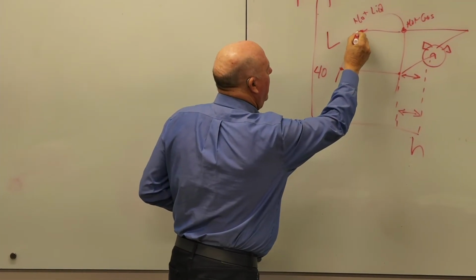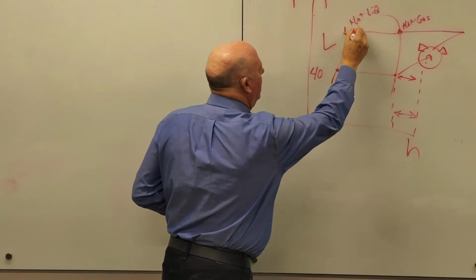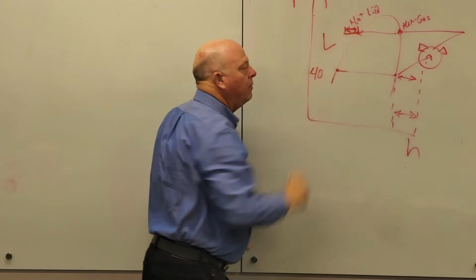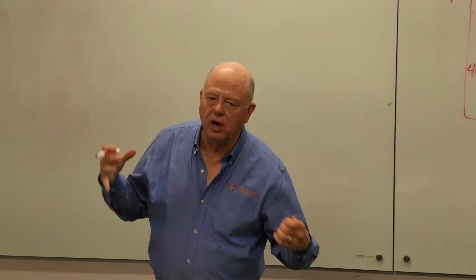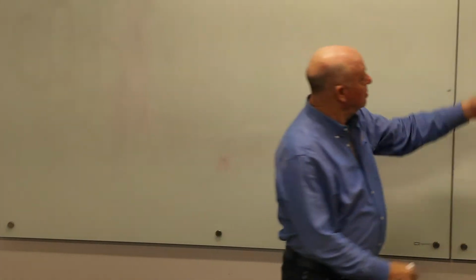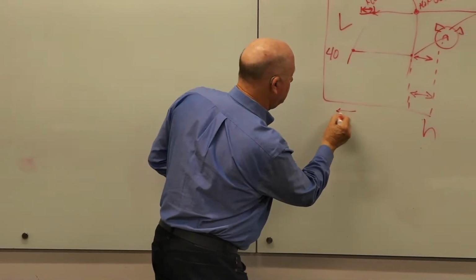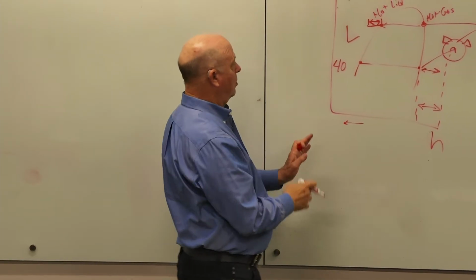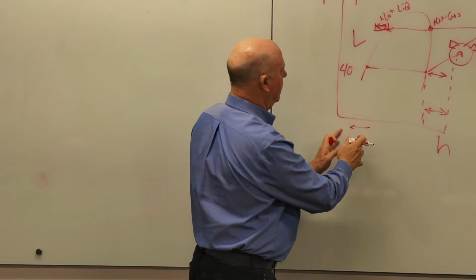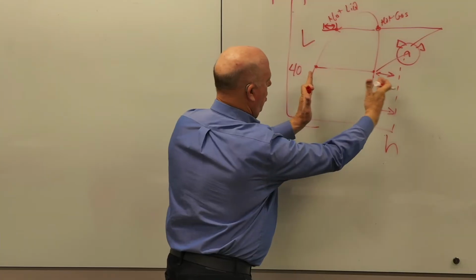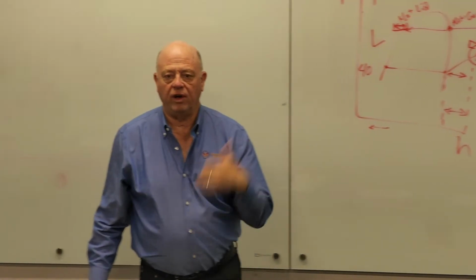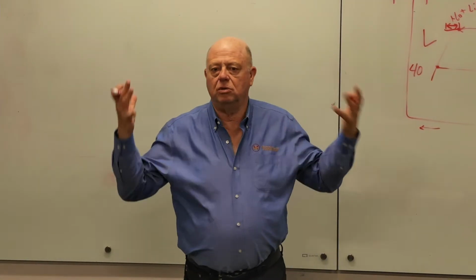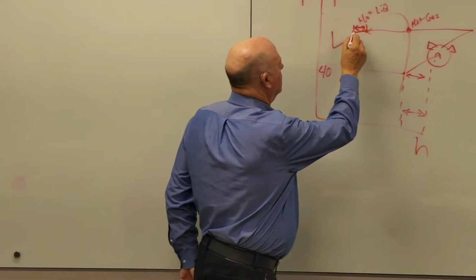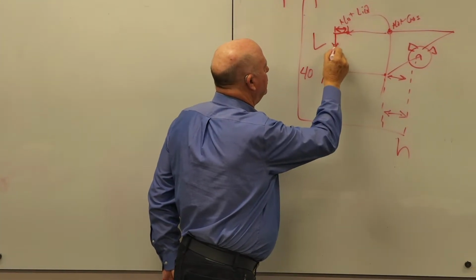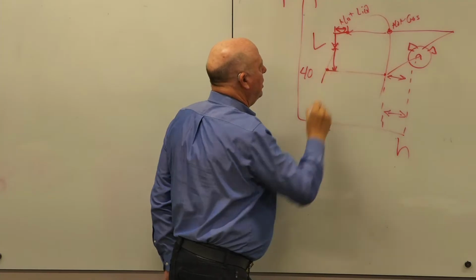To be sure that we got all liquid, we want to come over here a little ways and get some subcooling. Now I'm sure I've got all liquid. And you'll notice I've moved further this way. So that means that I am getting more cooling out of it if I give it some subcooling. So, that's good. We want to get some more subcooling. So we come down, we go through a change in state, we come down, and we intercept this line.